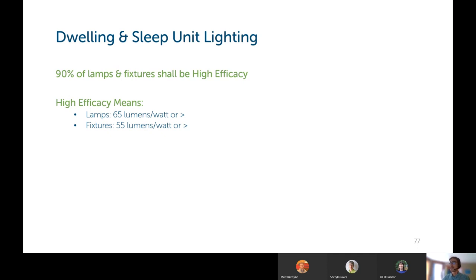Dwelling and sleeping unit lighting needs to have 90% of the lamps and fixtures installed in a dwelling or sleeping unit be high efficacy. And again, what high efficacy means is for lamps, 65 lumens per watt or greater, and for fixtures, 55 lumens per watt or greater.